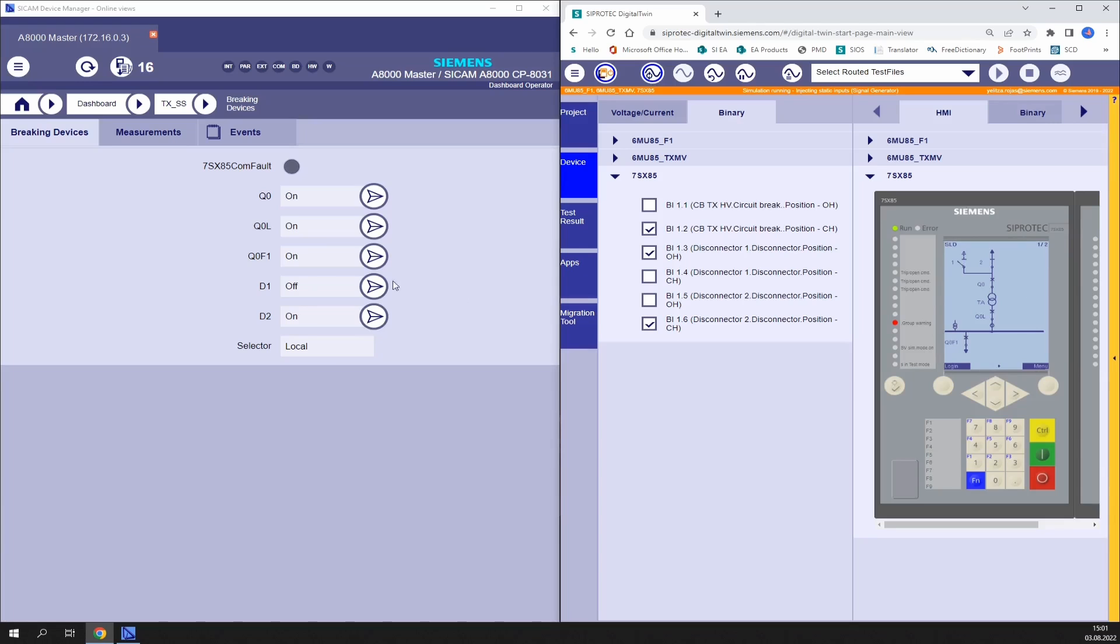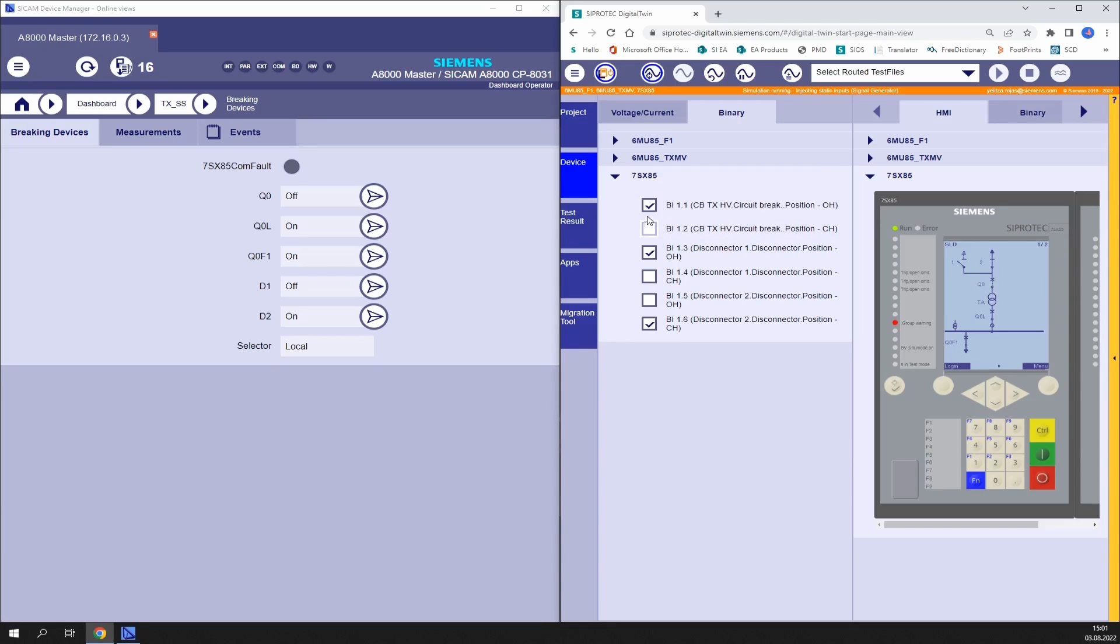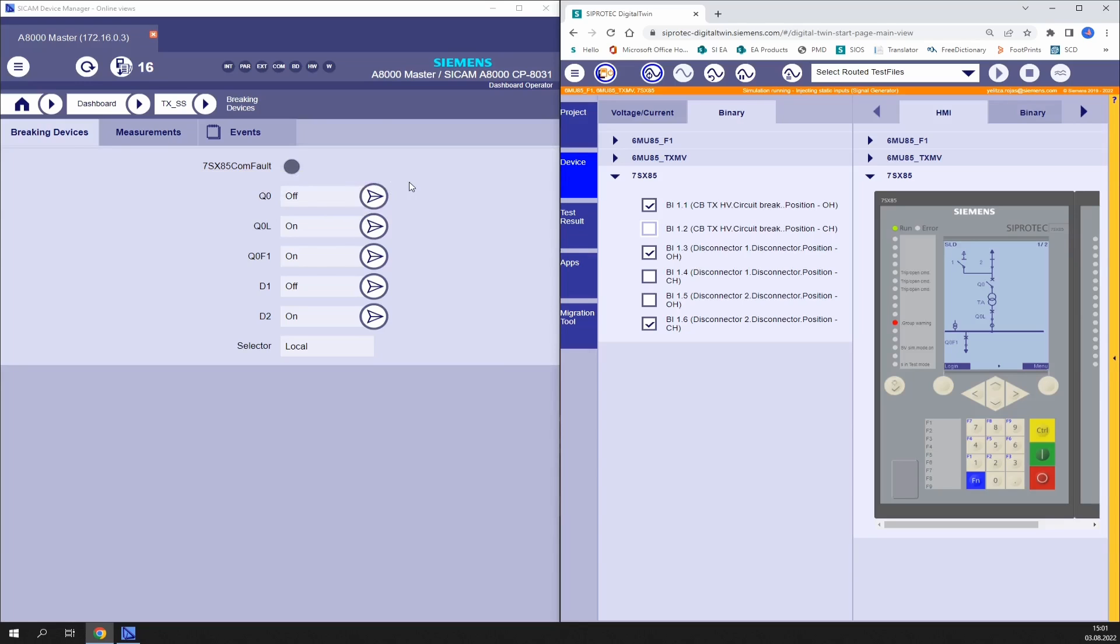We can force those switching devices to a specific position and validate the change in the A8000. Let's use the circuit breaker of the high voltage side of the transformer Q0 as example. We set the binary inputs of the relay and inject values. The status is updated in the device and we also see it is updated in the SICAM A8000. We can force it to open. We see it here in the display and if we go to the SICAM A8000 we see the same information.